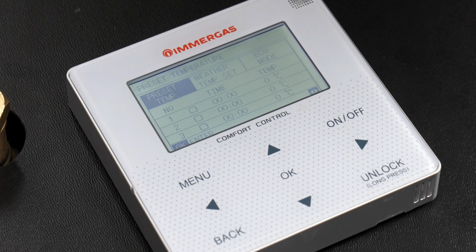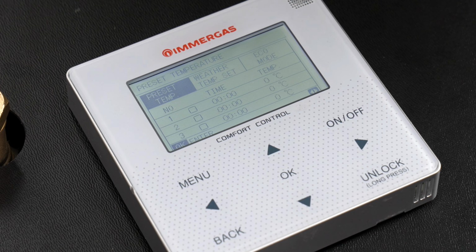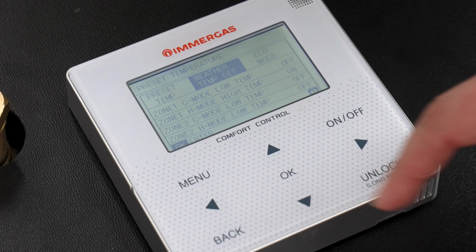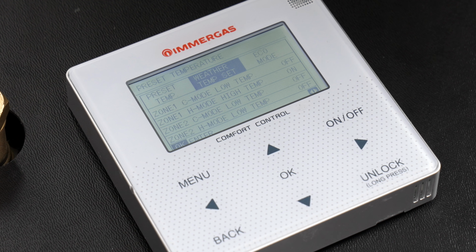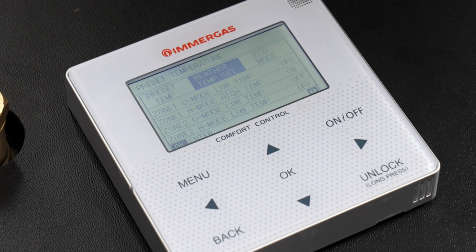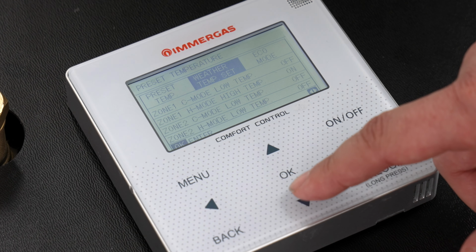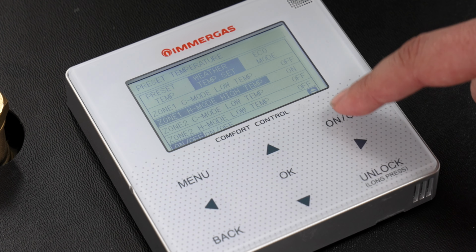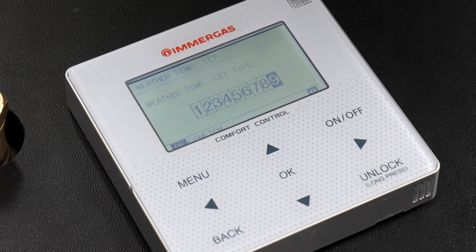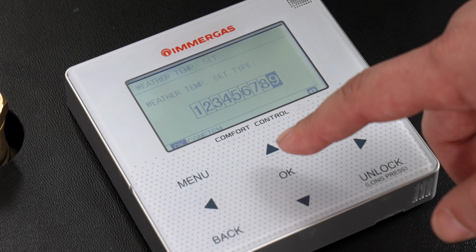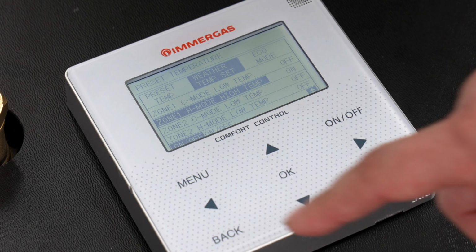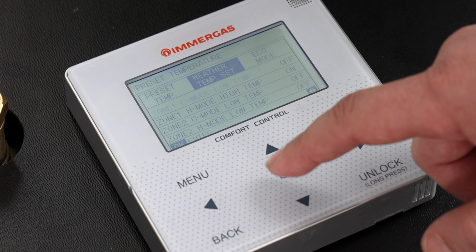Now what you can see in front of you is preset temp, weather temp set, and eco mode. We want to get into weather temp set. So we come across one. It now gives you a variation of choices, zone 1, zone 1, zone 2, zone 2. The correct one we are looking for will be zone 1, H/mode, high temp. You come down on the controller and you press on. Once you've pressed on, you will see that a set of numbers comes up. The number that we are looking for is number 9. So we'll click OK. Now that that's set, we'll press back and we'll press OK.